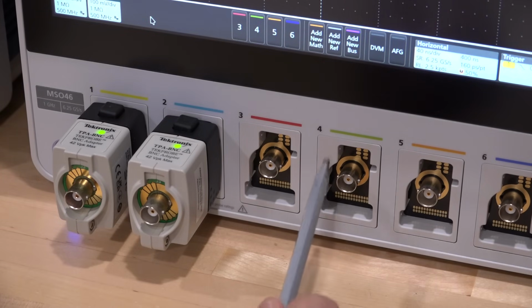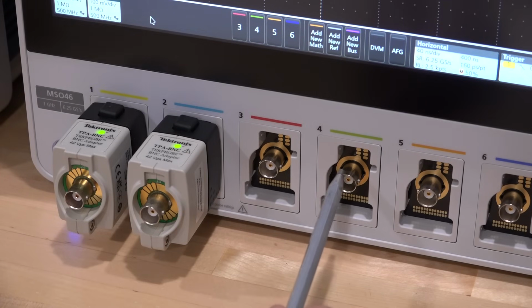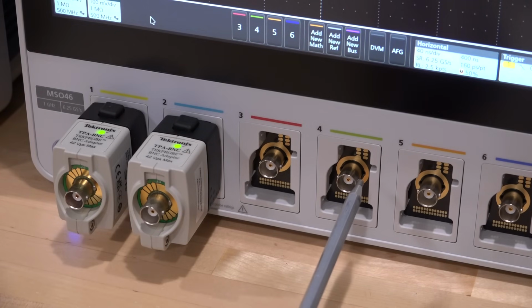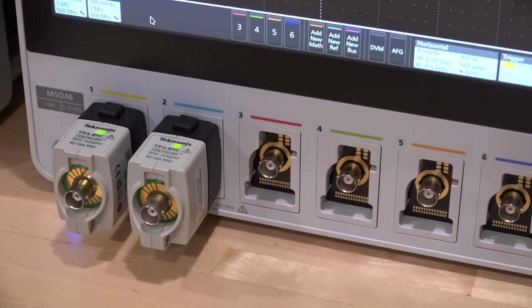There's also a low-speed I2C interface built into it, which communicates with the probe head and grabs calibration coefficients, model numbers, and essentially tells the oscilloscope what is connected to this. It's nice, I've gotten used to it, and it works very well.